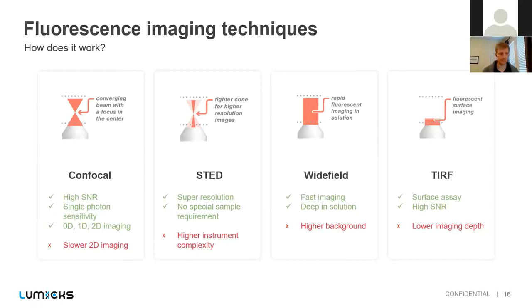Now, you can also have a system with either wide field or TIRF. If you've ever used an epifluorescent system, this is wide field. It allows you to image quickly, deep into a solution. However, because you're imaging through that solution, it's going to have a higher background noise. So if you're working at the surface, you may prefer something like TIRF, which will give you a much higher signal to noise ratio with that same fast imaging capability. And you do see a lot of labs that work with single molecule techniques use things like TIRF.